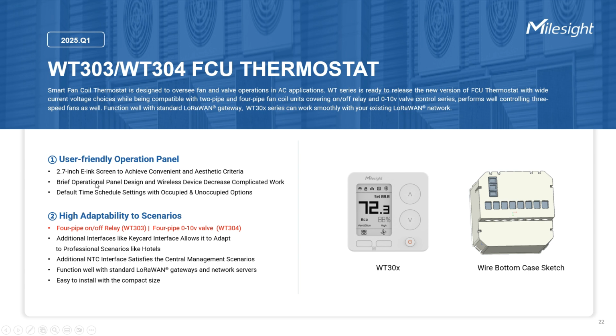If you only want a simple on and off operation, then the WT303 is right for you to control a 4-pipe system with a 2-wire valve by relay interface. If you want a more precise control of the indoor ambient, the WT304 is specifically designed for proportional control of 4-pipe systems with valve of 0 to 10 volts by providing a continuous voltage signal. The WT304 voltage output thermostat can modulate HVAC equipment to deliver just the right amount of heating or cooling.